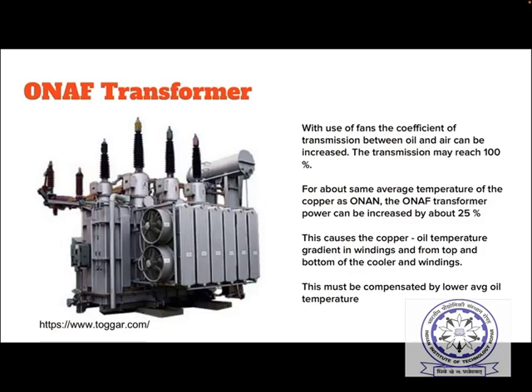Then the ONAF transformer. As you know, inside there is no change, oil natural. Outside, air forced. So as you see here, these two fans are extra compared to the ONAN transformer. What will happen with this? With the use of fans, the coefficient of transmission between oil and air can be increased. Oil is inside the tank and will flow through these radiators and exchange heat with the outer environment or air. So when you force the air using the fans, the transmission coefficient will increase. The transmission may reach 100%, depending on the situation, of course.